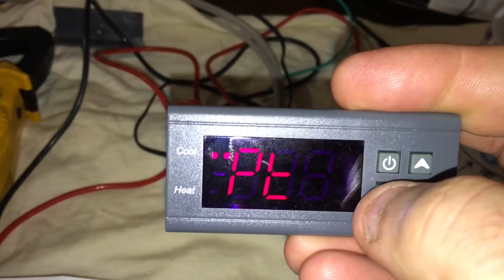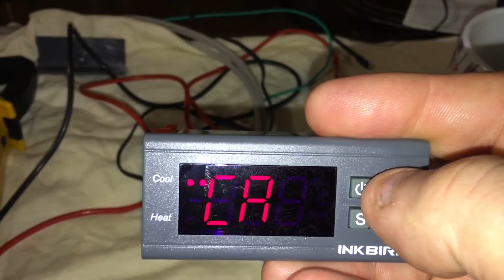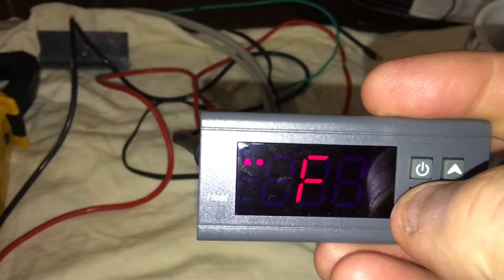Your protection setting. I got it set to 0 right now. You could set it for 5 minutes, like that. And you hit the power button real quick for setting that, and you hold that down 1, 2, 3. Temperature set 60. Differential set 10. Protection 5. CA, I think it's calibration. Yeah, temperature calibration value 0. Centigrade or Fahrenheit, Fahrenheit F.